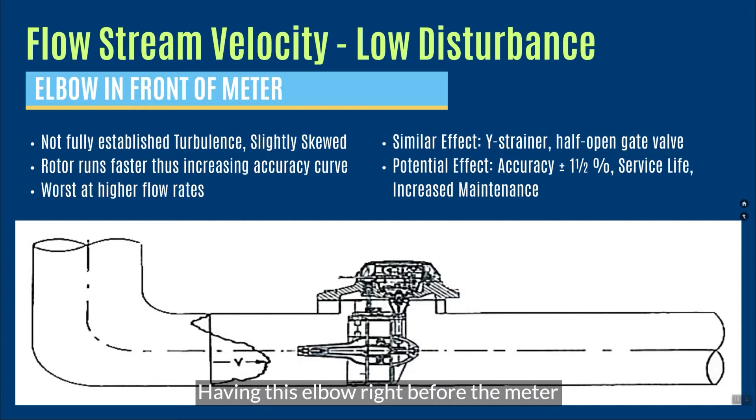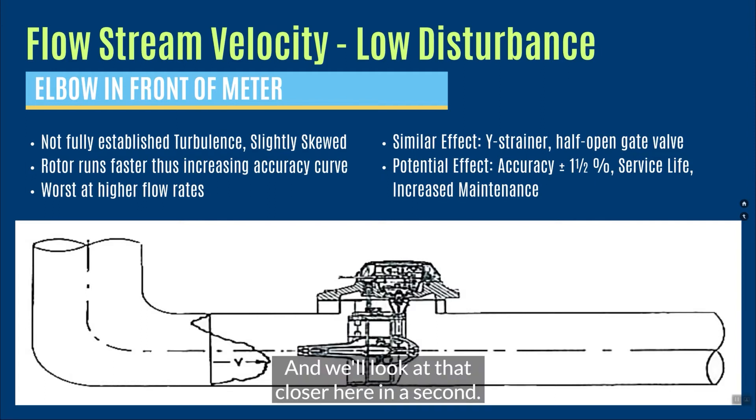Having this elbow right before the meter is going to give us a skew in velocity. Now what's going to happen here is this rotor is going to start to be pushed sort of in an odd way. And we'll look at that closer here in a second. The thing that I also want you to understand is this can have a potential effect on the accuracy of the meter.